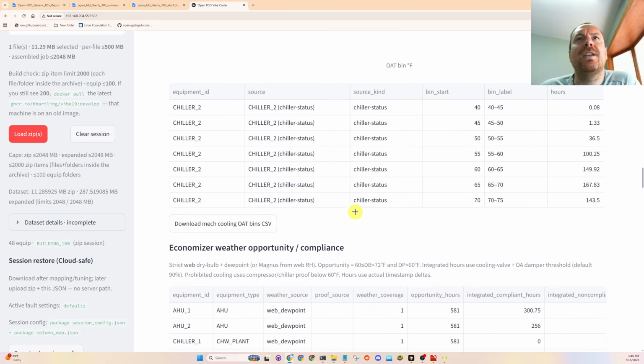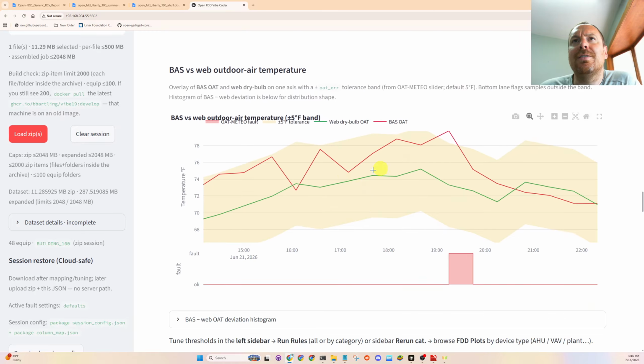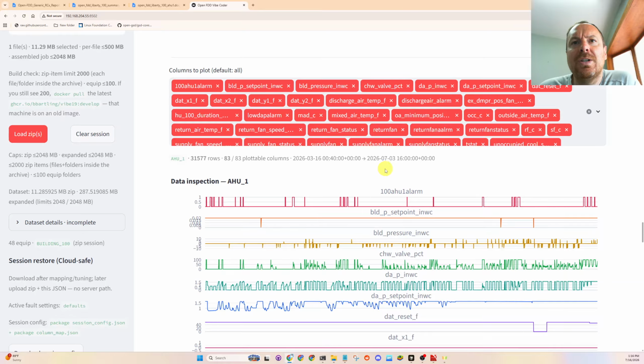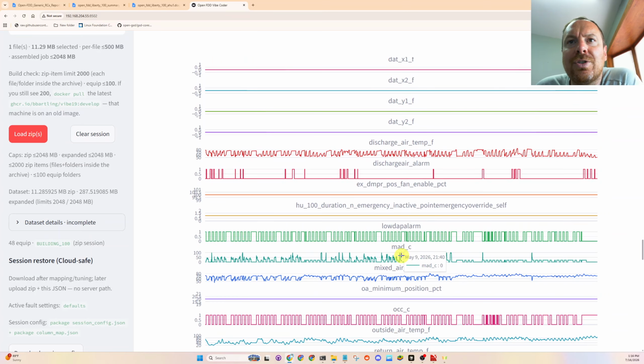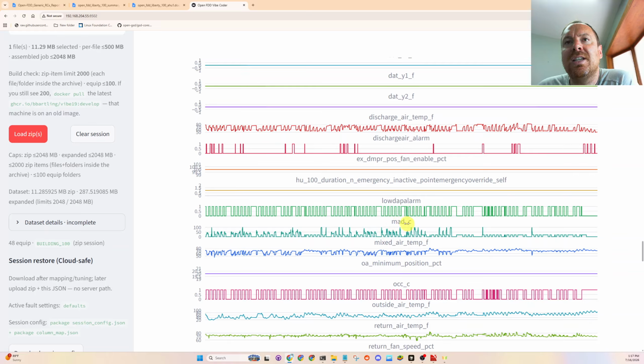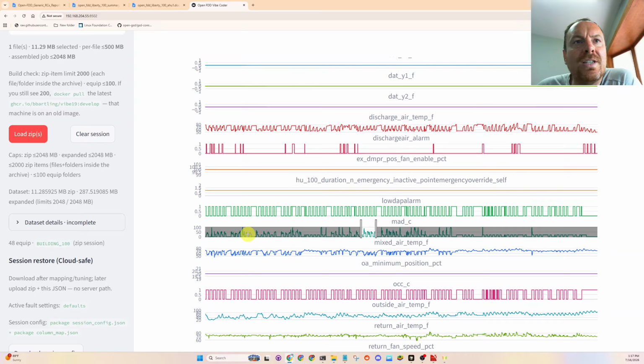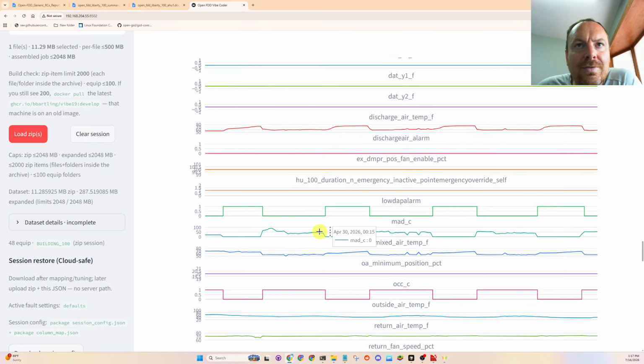I think we even had a histogram of the outside air versus web, but whatever. Okay, so this is another thing I wanted to show you guys, which is what I found out late in the day yesterday, that this MAD-C might be hard to see. That's the mixed air damper command, 0 to 100%. So this is the economizing damper. And as you can see, there's lots of squiggly lines, so it's economizing, which is good. So that's what we have to change in the data model, and I wanted to show you how you do that manually.